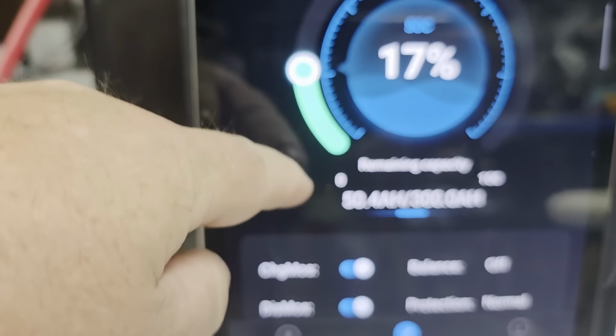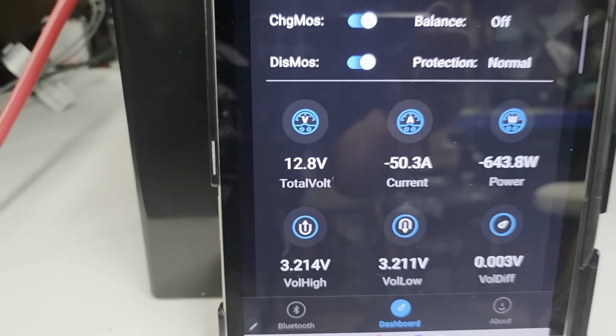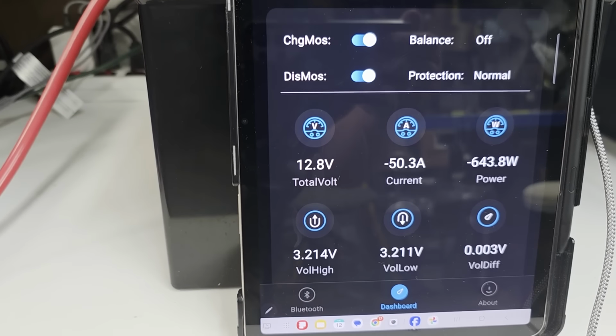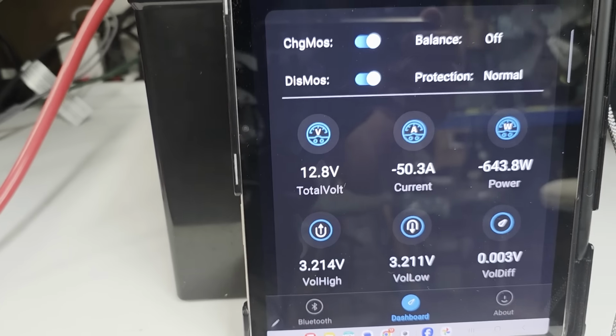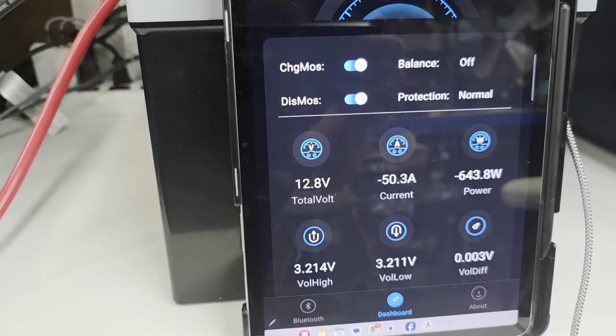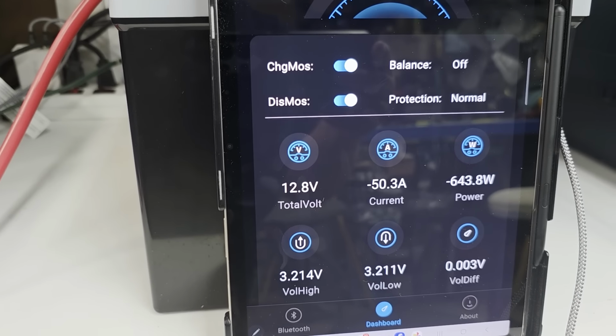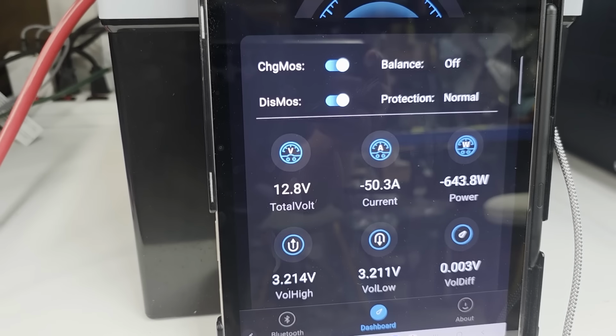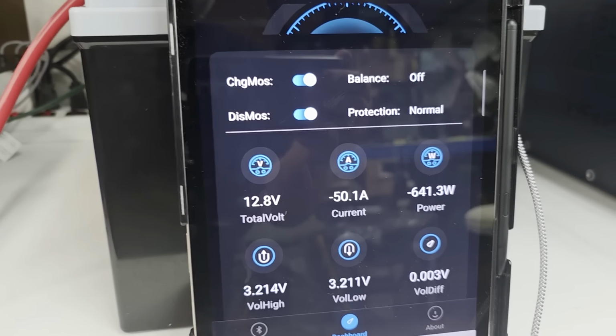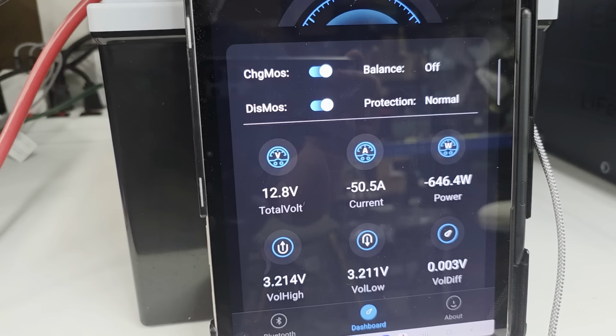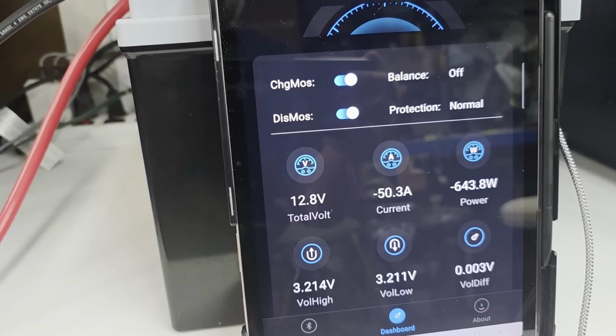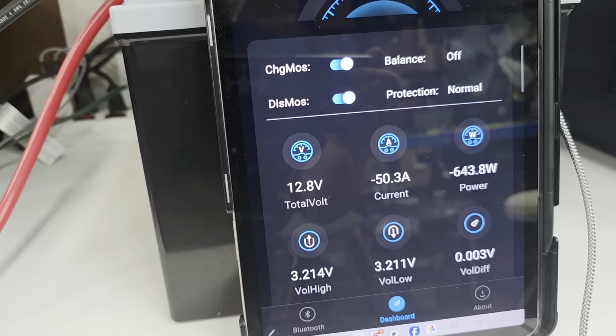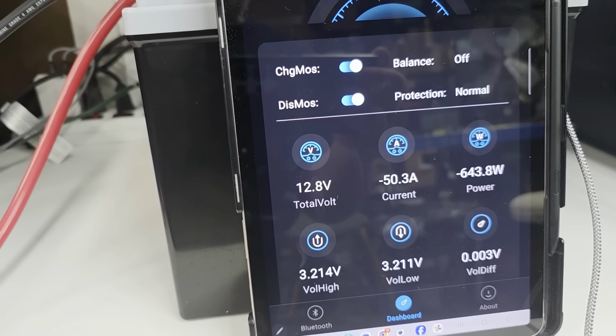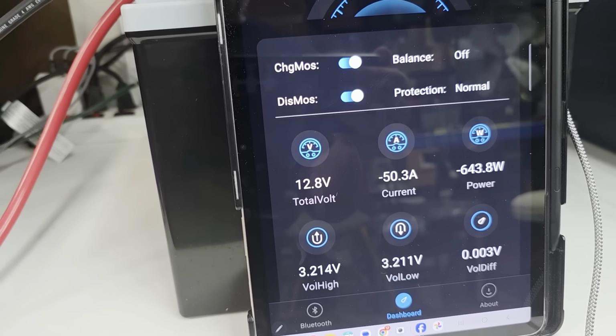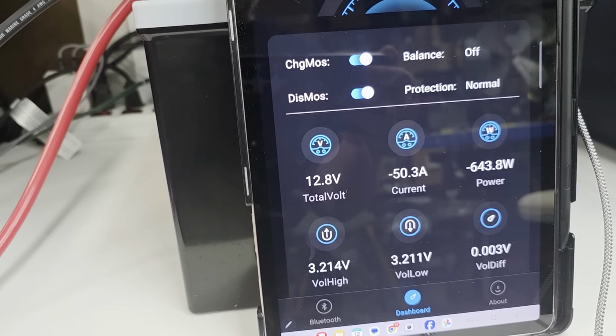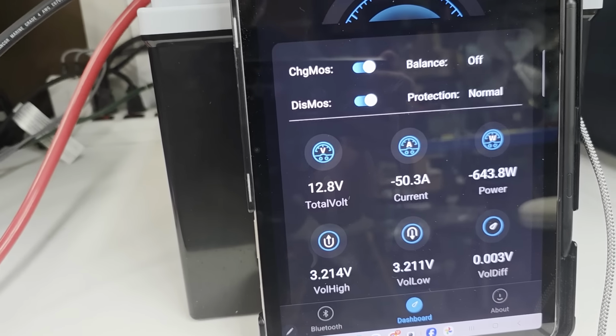Always balance SOC with voltage, cross-check them. Right now this is dragged down a bit because I have a 50 amp load on it, but if you check with no load, you can tell approximately where you are in SOC. It's very difficult to tell where you are if you're, say, 20% to 90%, because the voltage is so flat in that range. But it's easy to tell when you're approaching the lower knee or are deep in the lower knee or deep in the upper knee.